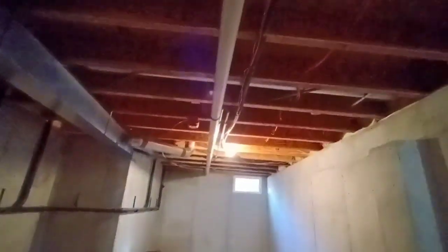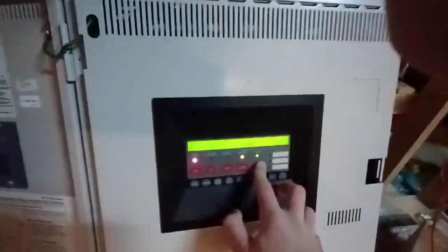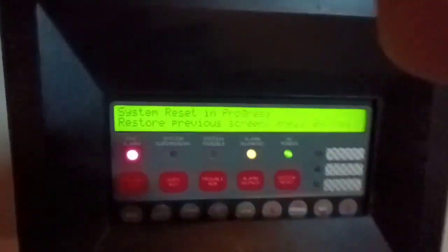We do have all the devices going back there and back here too. That strobe was on 30 candela if I didn't point that out already. We'll reset the system and go ahead and do a manual evac.